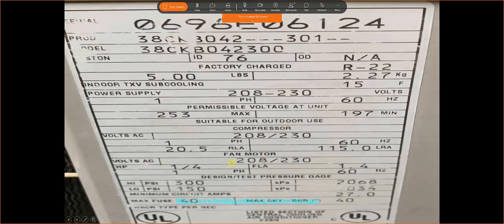Here's my fan motor information. Same thing, very similar to the compressor. We then have design test pressure. My high pressure is 300, my low is 150.